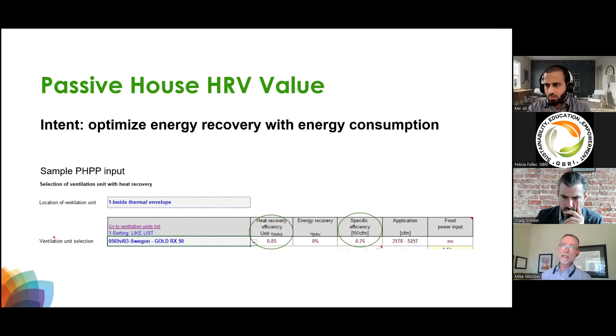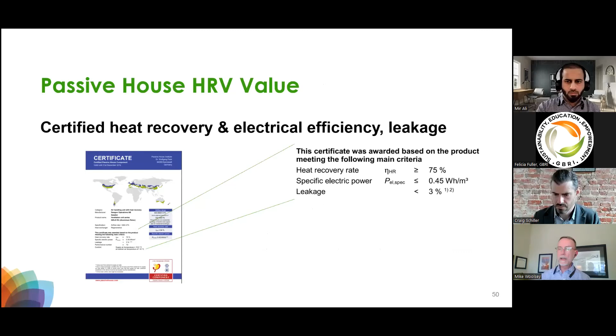Just like buildings are pass-fail, Passive House certified HRVs are pass-fail. To pass, you need at least 75% heat recovery efficiency and no more than 0.45 watt-hours per cubic meter. In inch-pound units, that works out to 0.765 watts per CFM.